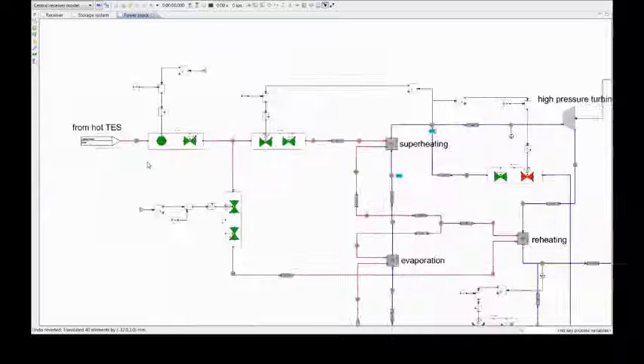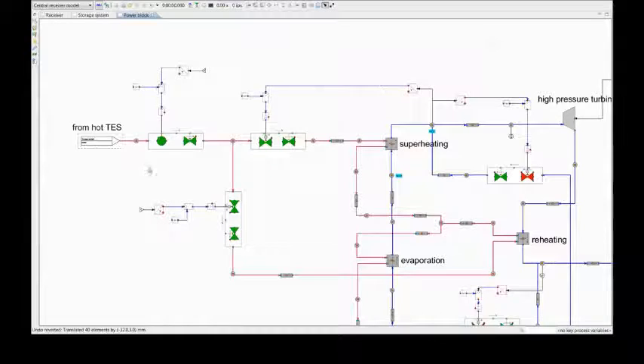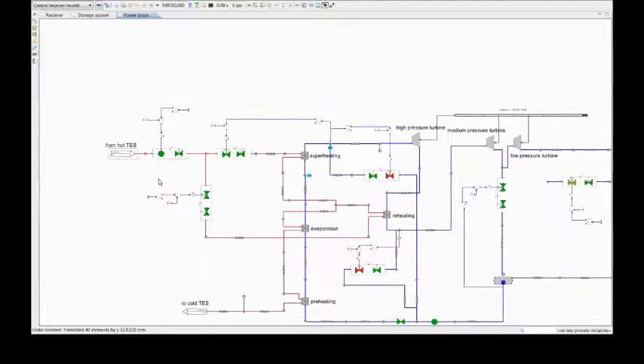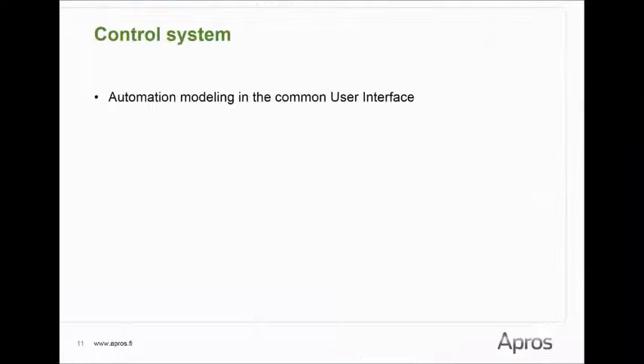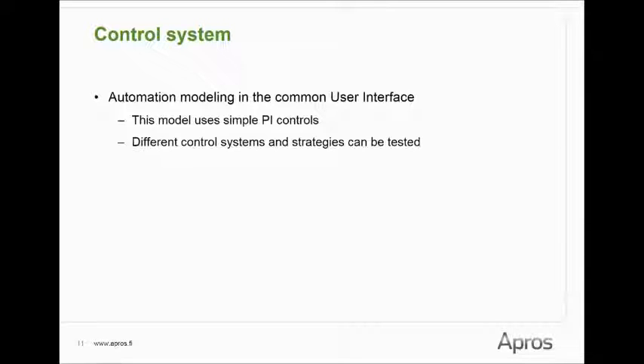All required control loops are integrated to the process models using the same graphical environment. The video shows the control loop for molten salt pump which transfers the hot salt from the storage tank to the heat exchanger train. This model uses simple PI control loops, but the environment is very flexible and open for trying out different control systems and strategies.